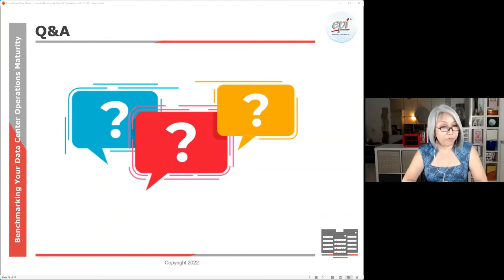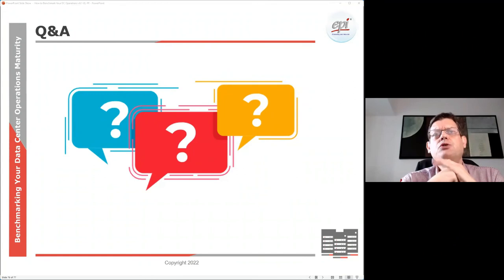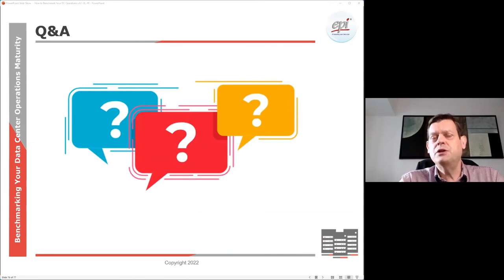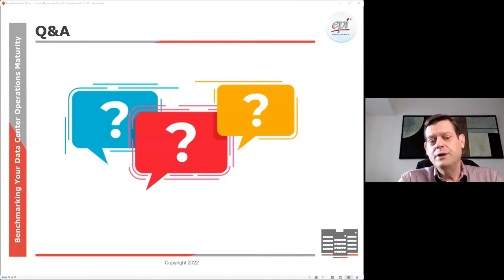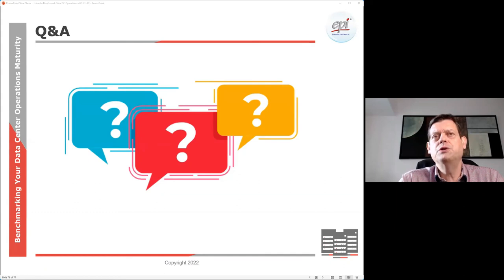Question: how do we avoid or minimize hardware faults like with UPS and generators? In the DCOS, in terms of maintenance procedures and all the things around them — including permit-to-work and related procedures — these are all described. In the appendix there is a very nice checklist that tells you all the things you need to check on various equipment, whether it's CCTV, a generator, a chiller, and so on — that serves as good guidance. It does not overrule vendor recommendations, but where applicable you can use it. The checklist plus the procedures described in facility maintenance would serve as a very solid approach to your overall maintenance program.